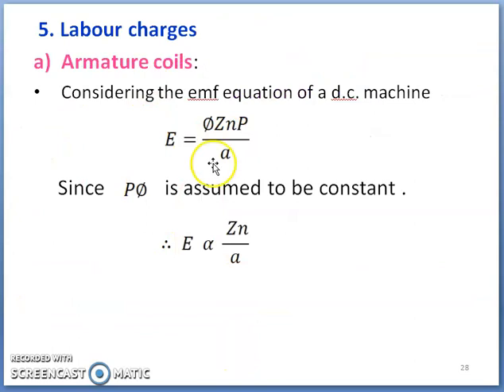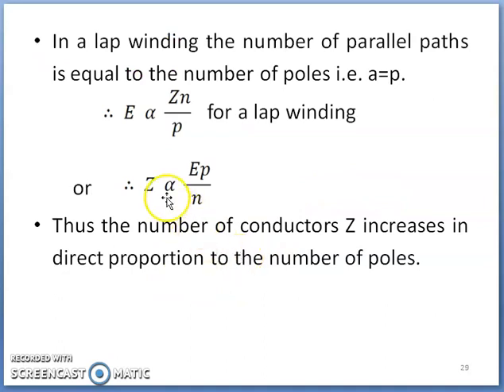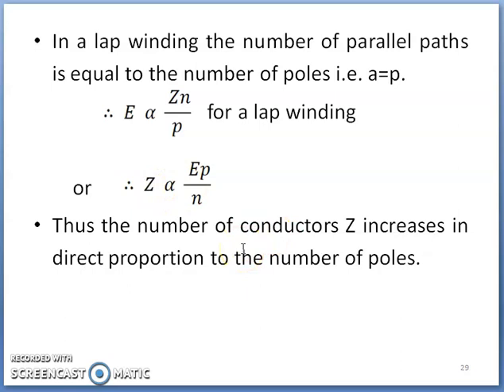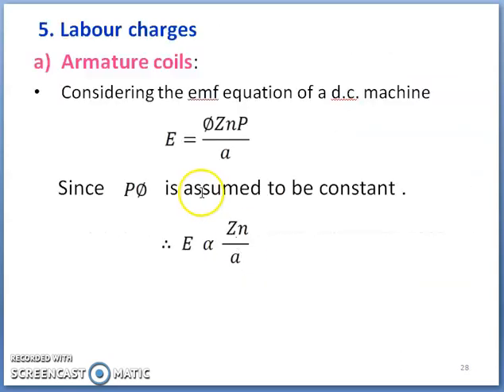Coming to labor charges. Considering the EMF equation for a DC machine, E = φZN/A. Since flux per pole is assumed constant, E is proportional to ZN/A. For lap winding, A = P, therefore Z is proportional to EP/N. This means if a large number of poles are used, the number of conductors will be more, and that will increase labor charges in the case of armature coils.